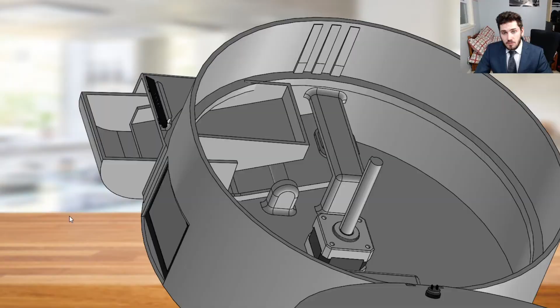To ensure that this device is safe, it will be ISO 13485 compliant. ISO 13485 is a quality management system directed towards medical devices. This quality management system will be followed for all stages of the product lifecycle. It also provides organizations with a medical device that meets both customer and regulatory requirements. The next step to ensure safety is UL certification. UL is a certified body that helps manufacturers with compliance with all applicable standards. When a device is UL listed, it means that all electrical components meet both Canadian and national electrical code.